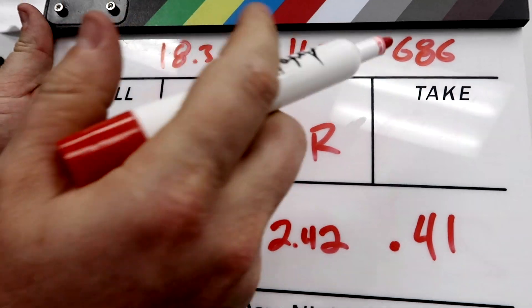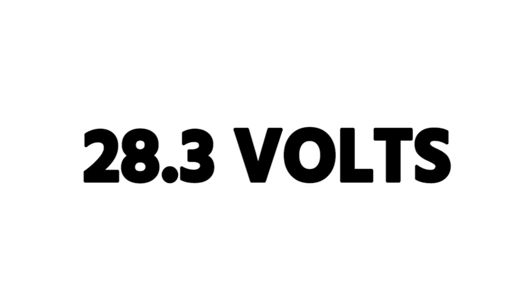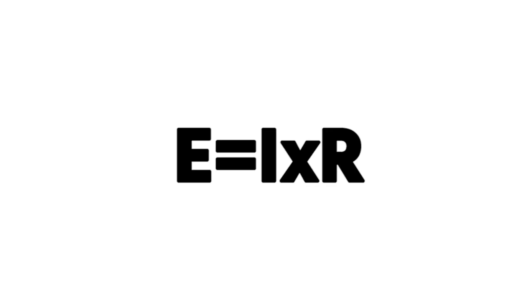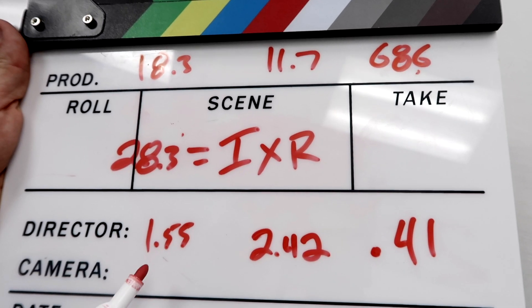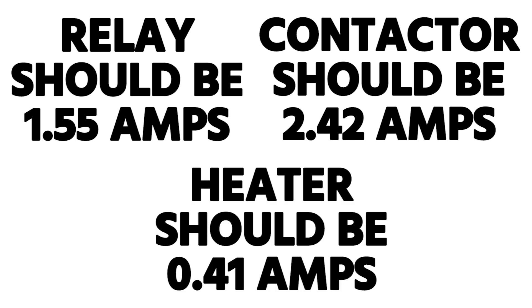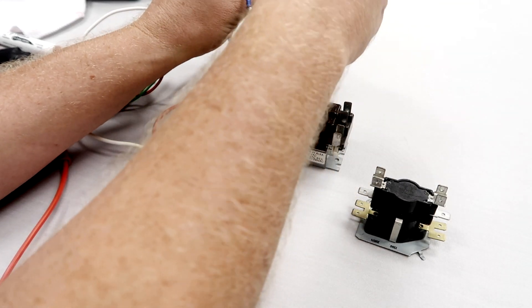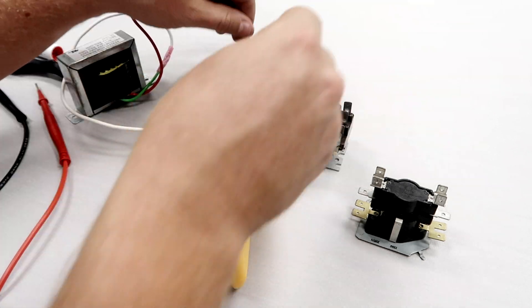Our resistances are 68.6, 11.7, and 18.3 ohms. We know our volts are 28.3. The formula is E equals I times R, or V equals A times R. Based on our calculations, our amps for the relay should be 1.55, for the contactor should be 2.42, and for the resistive load — the heater on our stack sequencer — should be 0.41. Let's see what we actually get, starting with the contactor at the predicted highest of 2.42.